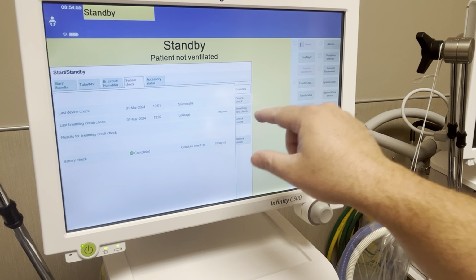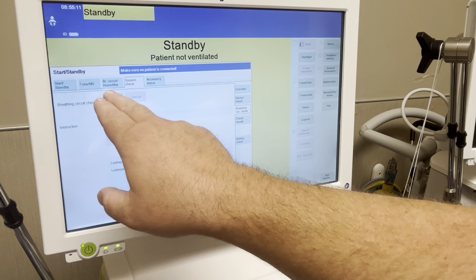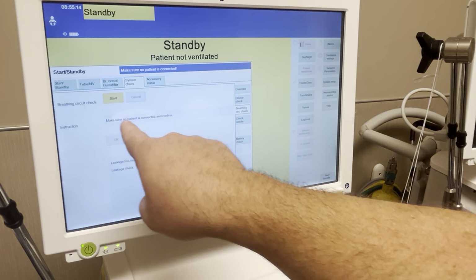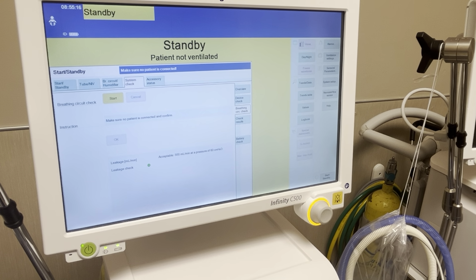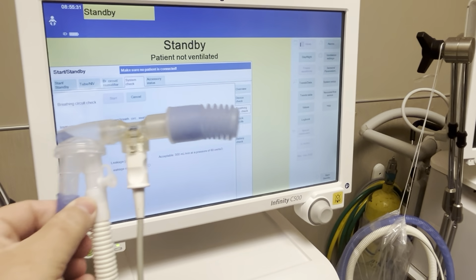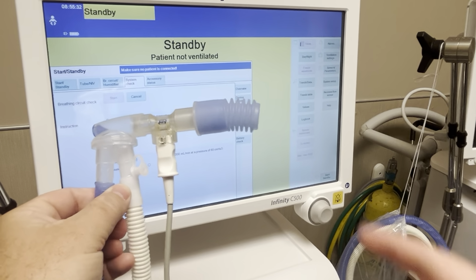Okay, so we'll go to breathing circuit check first, just to make sure I don't have any leaks in this circuit. Hit start. It tells you here, make sure no patient's connected, and confirm, which you do with your knob. And then it says connect breathing circuit, to patient connection port, and confirm with OK. So our ports are sealed anyways with the lung. The lung will be fine as long as it doesn't have a hole in it. So I'll push OK, and it starts doing its thing.